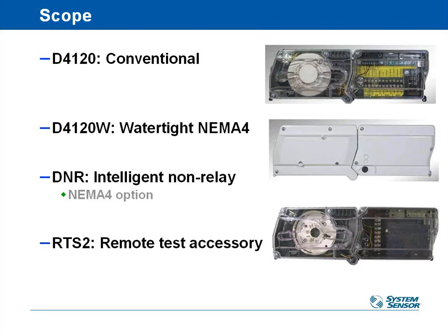There's intelligent detectors, which means that you can use communication to communicate between different detectors to alarm each other, and also alarm back to a main panel. That is a proprietary thing, as with all manufacturers of smoke detectors, and this would be specific for the System Sensor Honeywell type product. It wouldn't work with other parties.